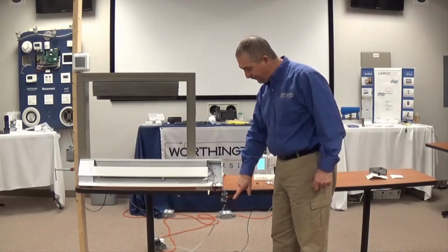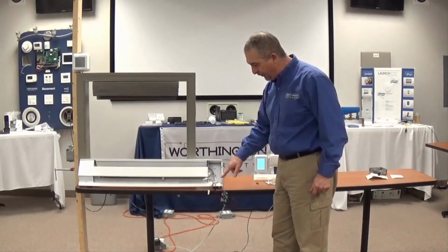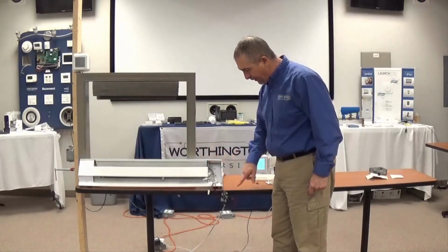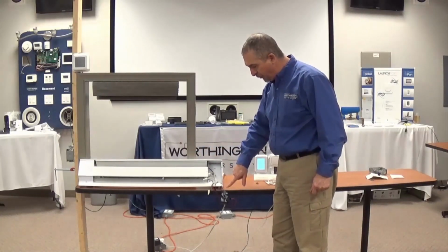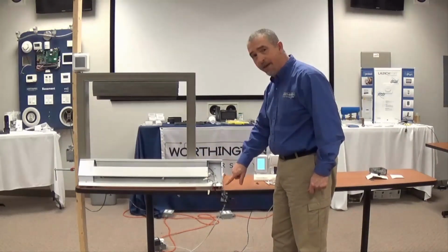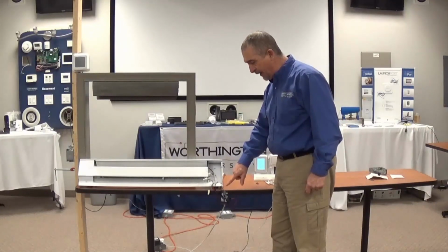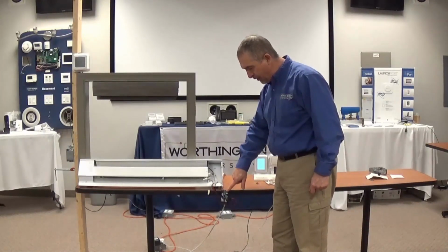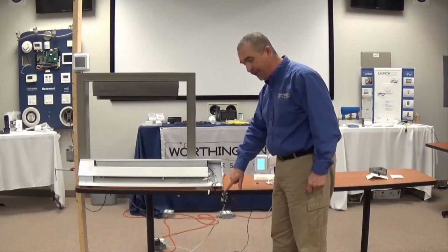This is the module, and it's tied into the line voltage feed and to the load for the heater. This connection here is the low voltage to feed the thermostat. This will power a 24 volt thermostat whether it's battery backed up or not. You have your hot, your white, and your common.